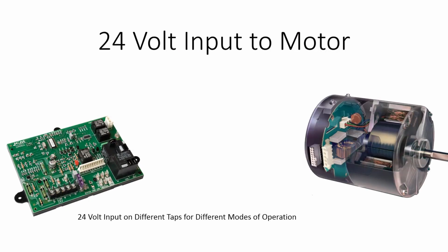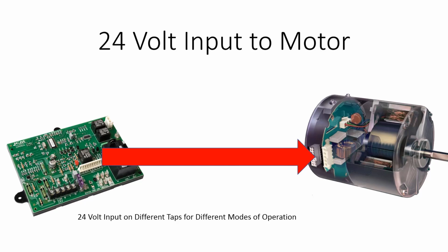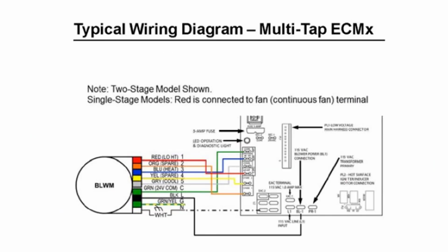The third type of communication to the motor is just a 24 volt input to the motor. The board sends a signal of 24 volts to the motor, and the CFM and torque and RPM data is stored in the electronics of the motor. So depending on what tap you're energizing, the motor will know where it needs to run for that mode of operation. This is a typical wiring diagram of a multi-tap ECM motor.